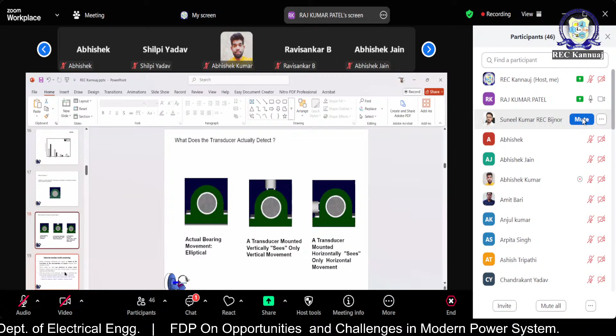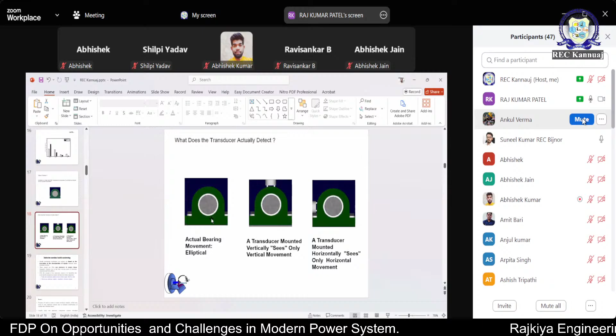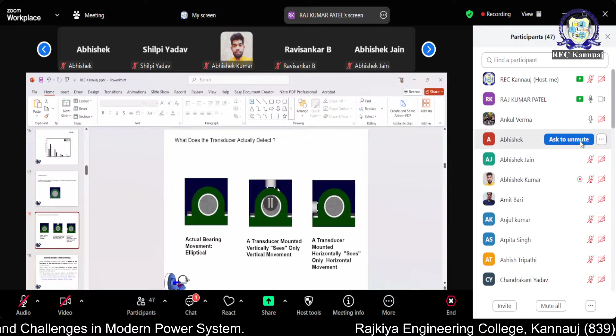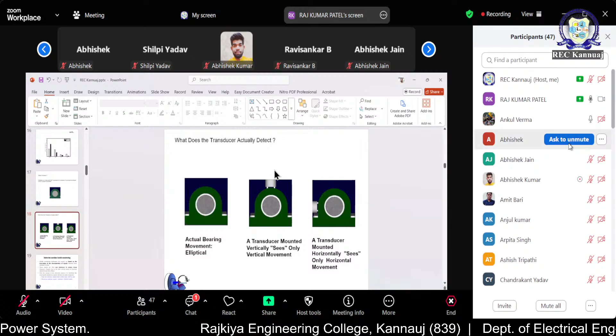What this sensor actually detects, if this is the actual bearing movement, it's a cyclic movement. The sensor we can mount on the top, or we can mount it horizontally. So based on that, if we mount it on the top, the vertical movement will be detected, and if it is mounted horizontally, it will detect the horizontal movement of that bearing.